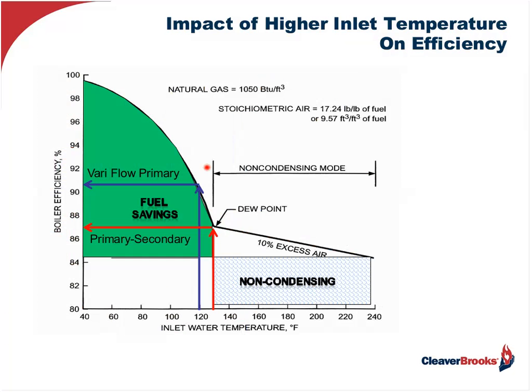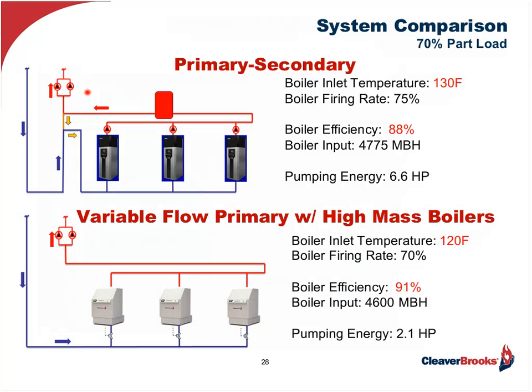Again, this chart that I showed you before, the low mass primary-secondary boilers are operating at about 87 or 88 because the water is only 130. The high mass variable flow system is operating at 120, so it's operating at about 91% efficient. We're maximizing the efficiency of those boilers. Now, this is just the same slide. You can just see the differences again.